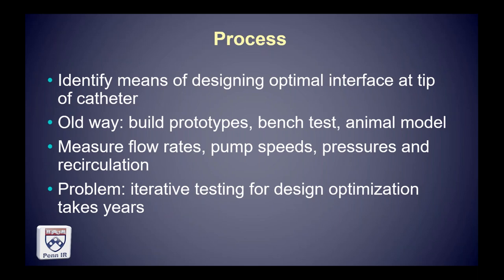Recirculation is an important concept in dialysis — it means already dialyzed blood is going through the dialysis circuit again through the membrane and machine, thereby diminishing the efficiency of hemodialysis. So you want the least amount of recirculation possible. The problem is this iterative testing for an optimal dialysis catheter design takes years because of the lack of accuracy and reproducibility in bench testing and animal models.